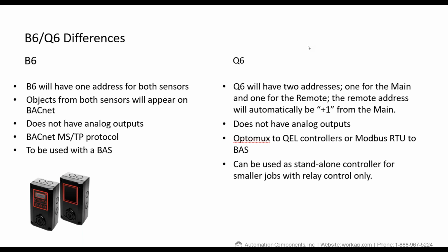And another big feature on the B6 is, say you've got the combo of those CO and NO2, it only has one address for both sensors on the BACnet. So you won't have an address for NO2 and CO. You'll have one address for both, which is pretty big when you're running, say, 10, 20 sensors on a project. You may not have to buy another JACE or whatever control system you're doing.